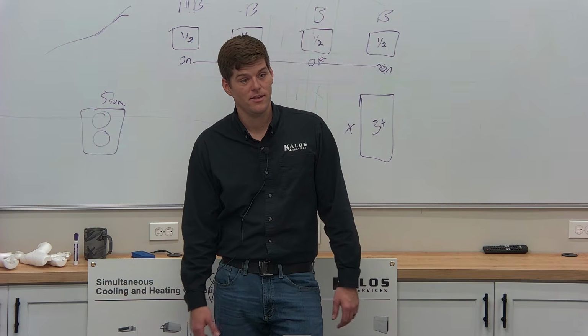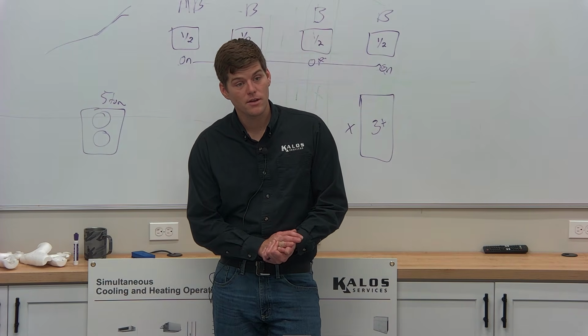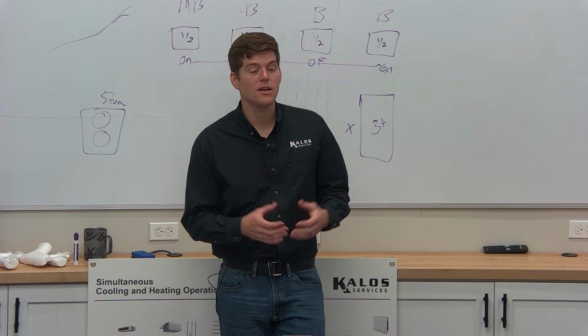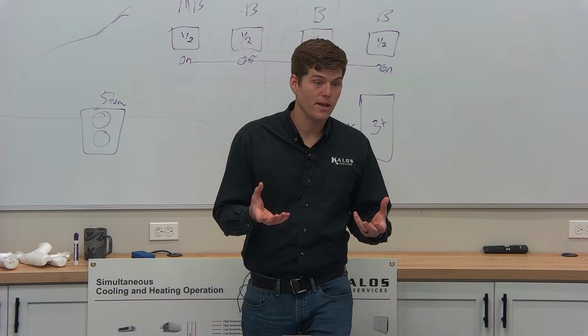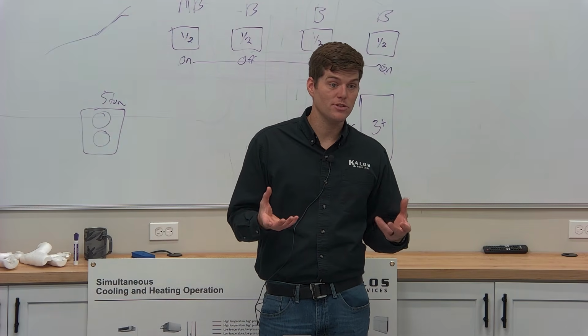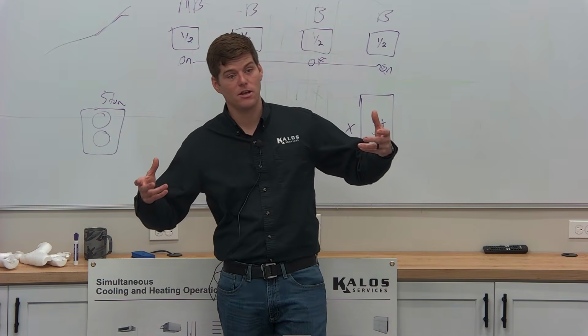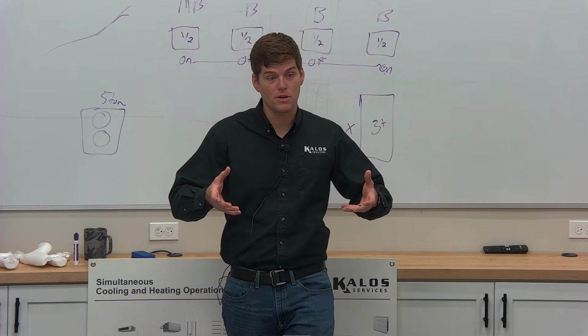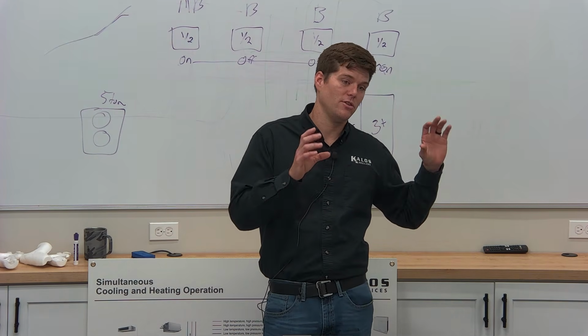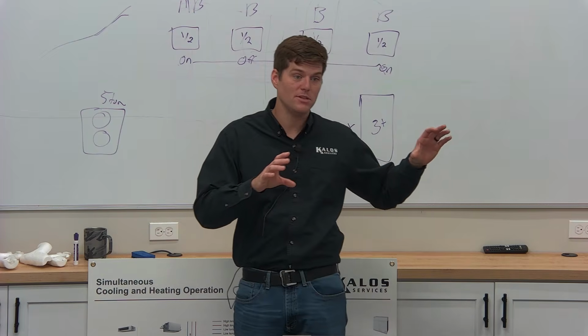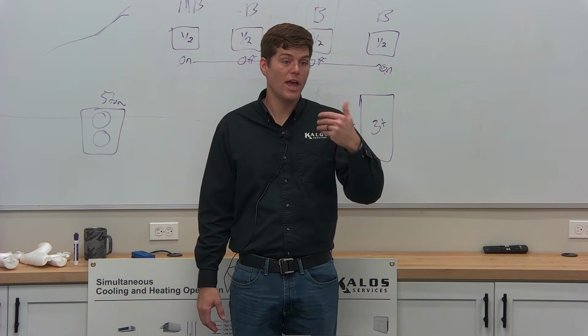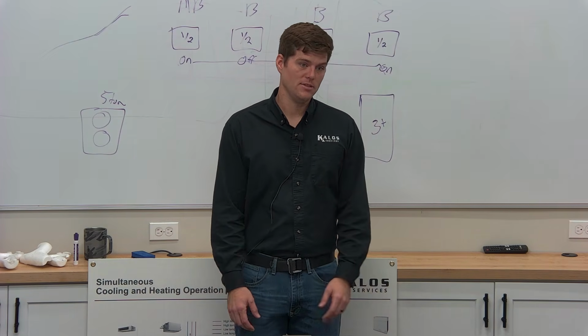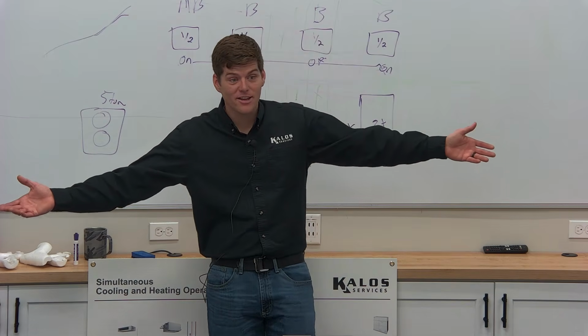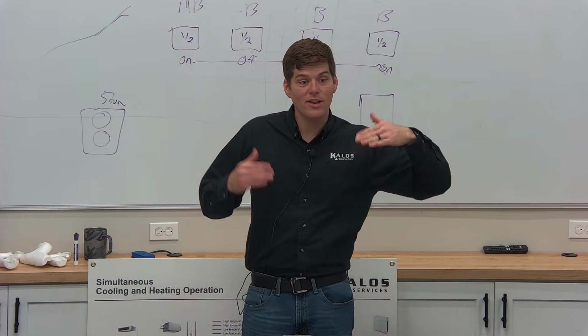How about vibration? Vibration for what? You shouldn't have vibration. Fan motors are isolated on rubber grommets. It's a DC-driven fan motor. The unit is balanced for efficiency, and when it's hung, it's even on rubber grommets itself. So there should be no vibration from the indoor unit, or any micro vibrations on the actual hanging rod or the pipe itself, to cause any kind of issues. If your pipe is supported correctly, you won't have any additional weight on there.